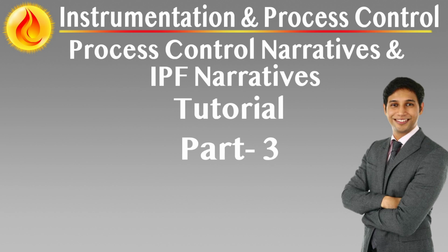Logic matrix. An X is placed in the matrix cell where an initiator triggers a particular final element, showing the logical relationship. Multiple initiators may be required for one action, or a single initiator may result in several effects. IPF marking. Protective functions that form part of an IPF are clearly identified in the matrix.